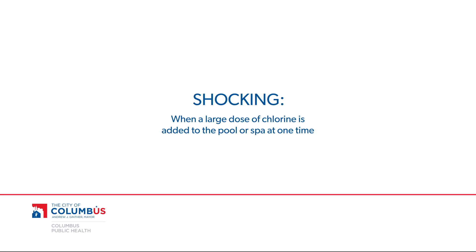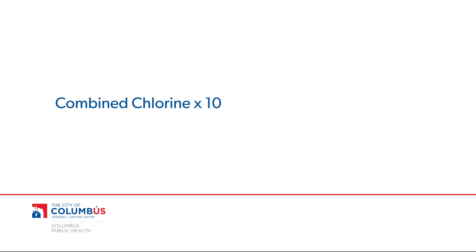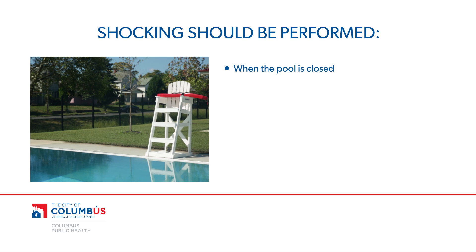Shocking is when a large dose of chlorine is added to the pool or spa at one time. The dose should be 10 times the amount of combined chlorine, subtracting the existing free chlorine level to achieve breakpoint chlorination, which will eliminate combined chlorine and increase the free chlorine level. Shocking should only be performed when the pool is closed and in the evening after patrons have left to allow the disinfectant to properly circulate.